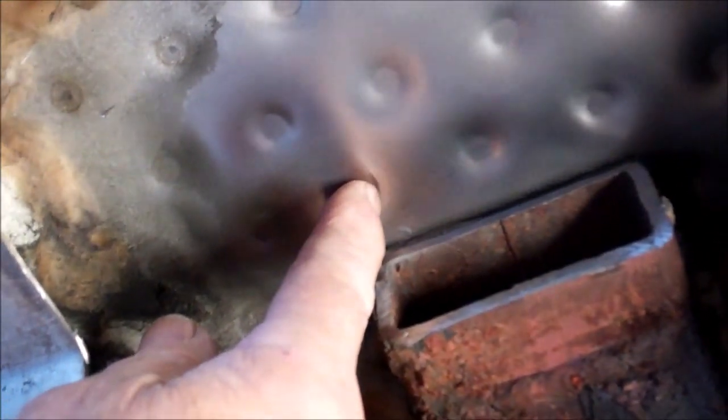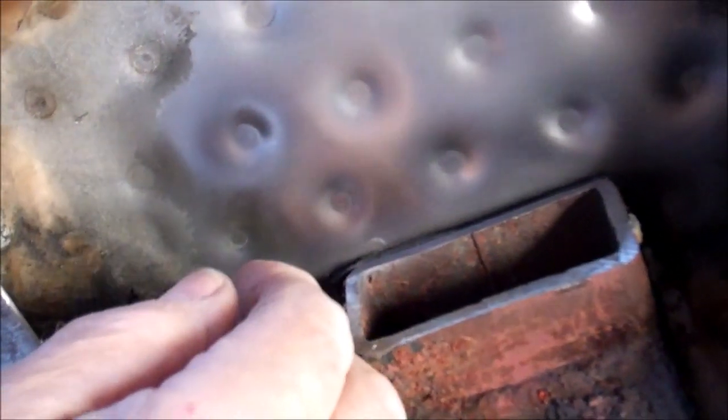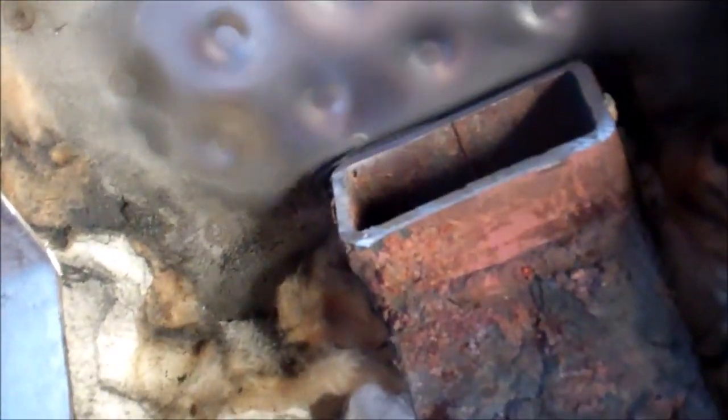I'm going to be welding these three in this row, and I shall also weld the four in this row. I shall also set a reinforcing plate which will sit on to my repair welds, and that'll stop the evaporator from getting squeezed, which is what has caused the leak in the first place. Then I shall build a couple of gussets which will come down onto the steel frame down here. Next thing to do is get these spot welds welded up.